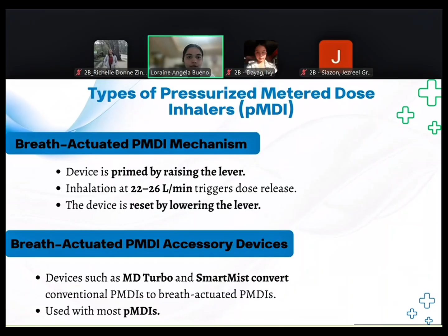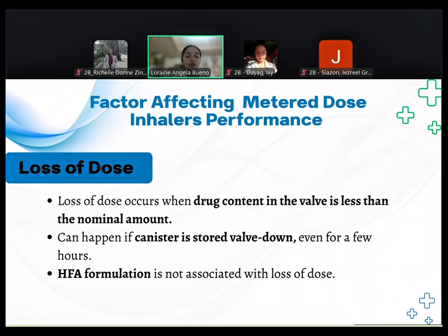Here are the factors affecting metered dose inhaler performance. Number 1 is loss of dose. Loss of dose occurs when drug content in the valve is less than the nominal amount. It can happen if the canister is stored valve down, even for a few hours. Hydrofluoroalkane formulation is not associated with loss of dose. This means loss of dose happens when the valve of the metered dose inhaler lacks medicine even though the discharge seems normal. It often happens when the canister is stored valve down. With hydrofluoroalkane formulations, there is no problem with loss of dose.